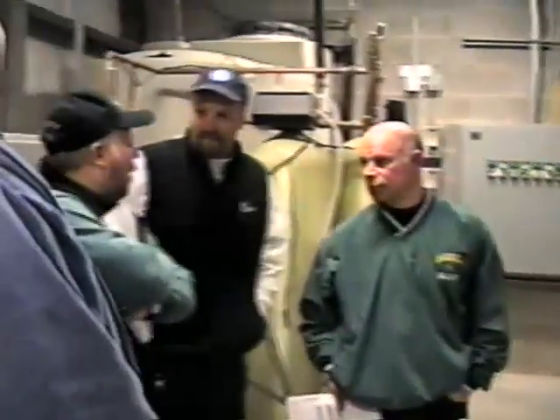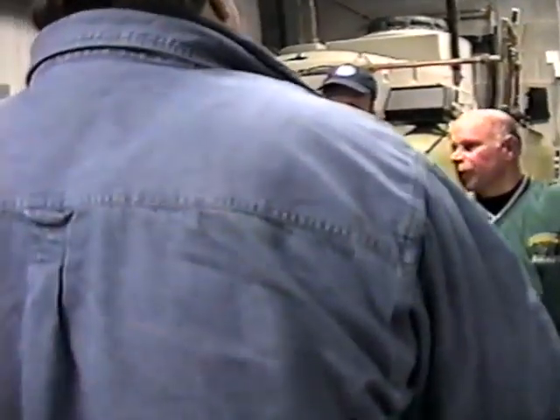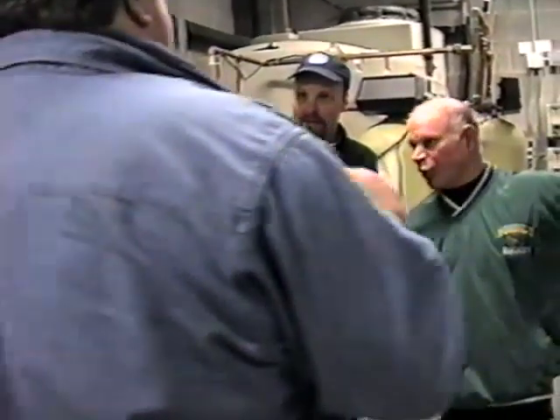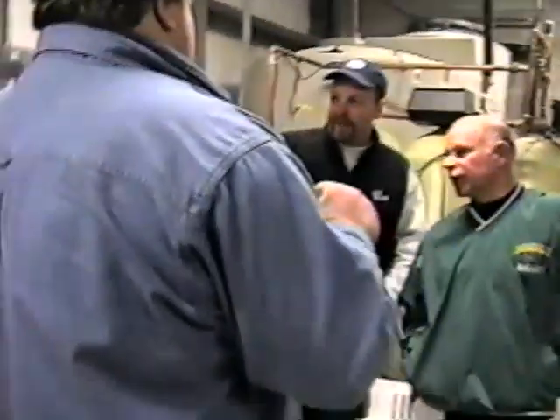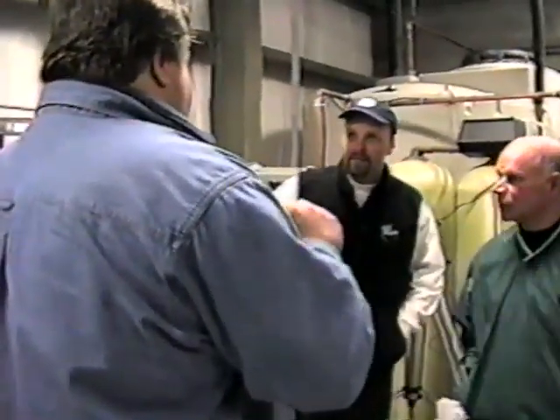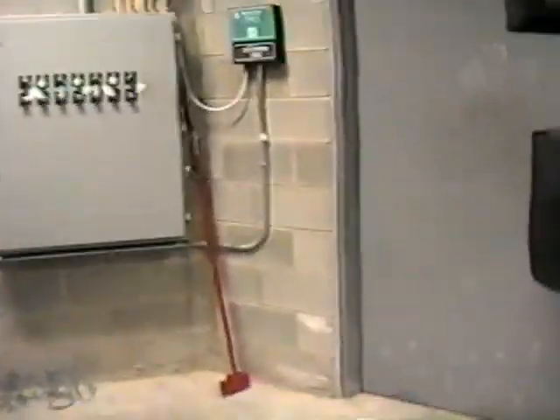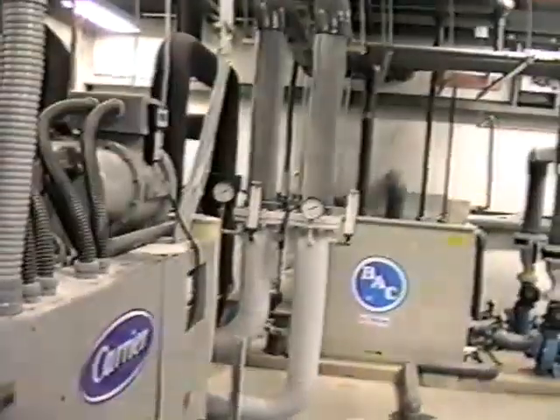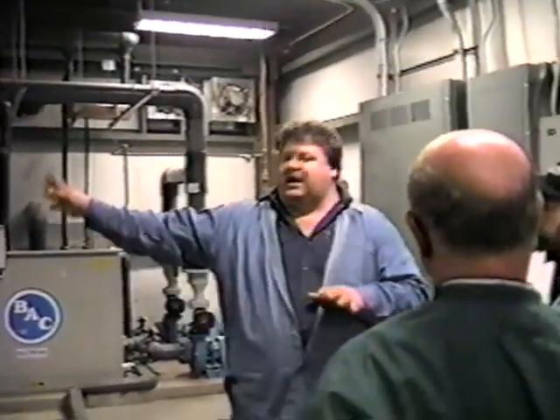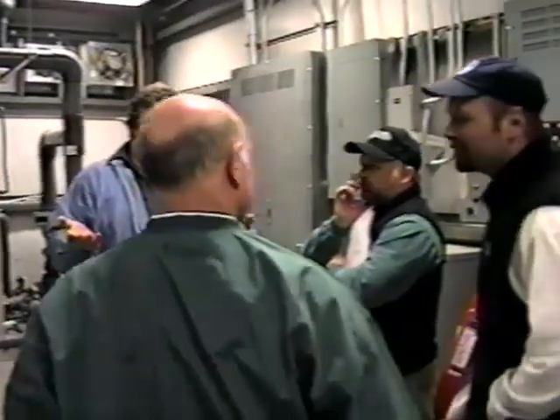Yeah, but wear out A. No, but isn't that programmed so occasionally B doesn't have any hours on it? That's what he said, it's supposed to do that. Right, the reason you got so many hours on there is because to this point, you have to make sure that it's done. Let's say A came on, and it's run. B came on only when you needed a little extra. B shut off, but A never did. It kept running. So number of starts could be close, but actual running time is going to be different.